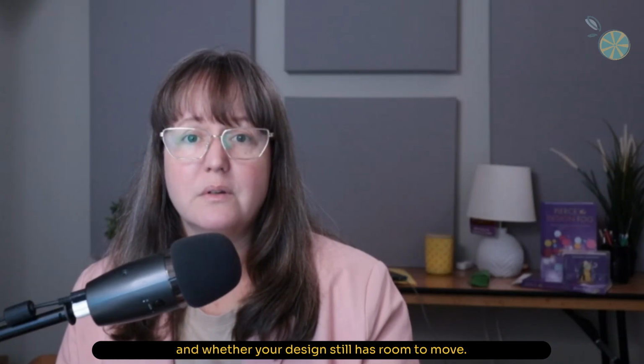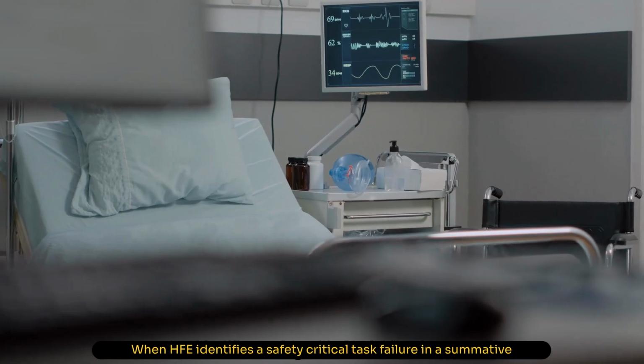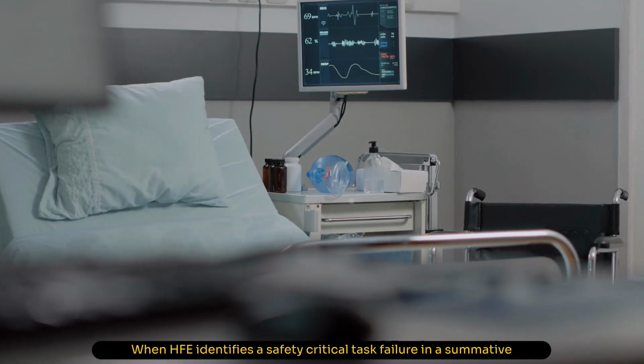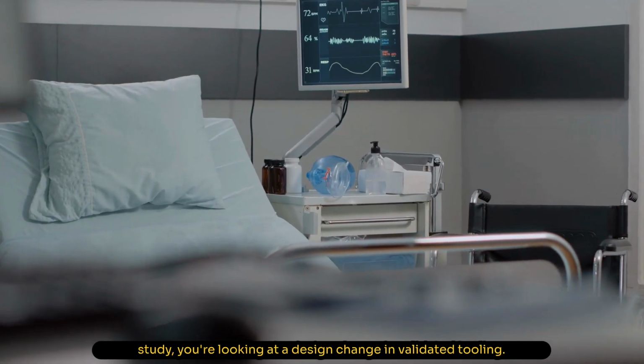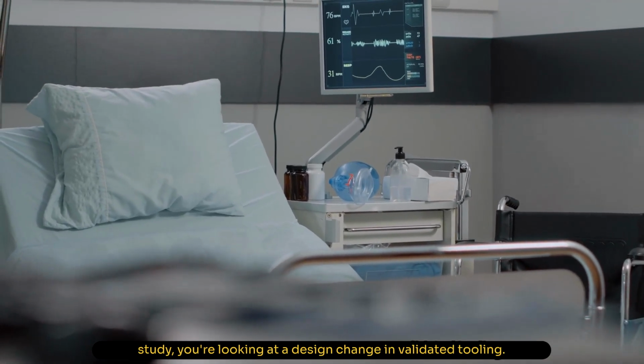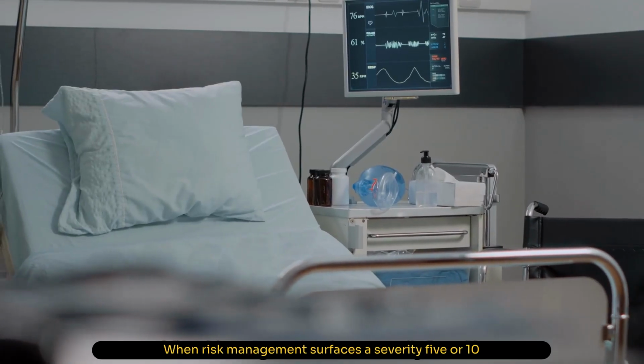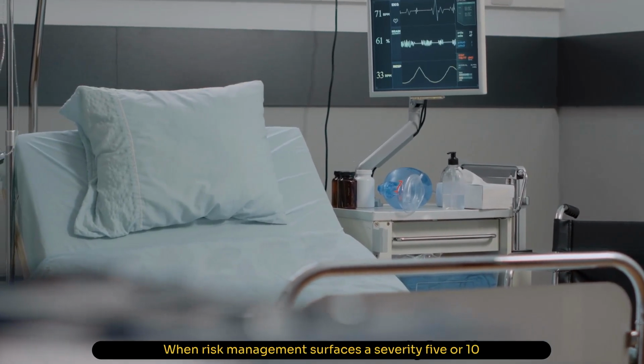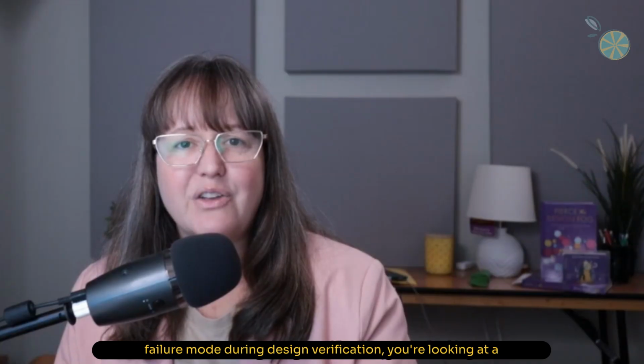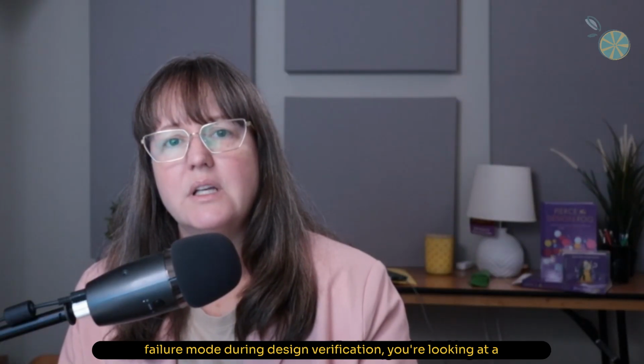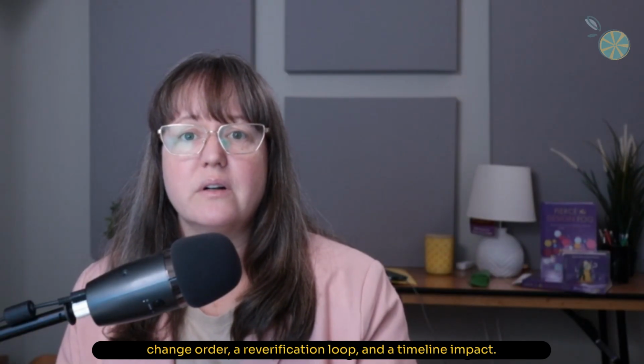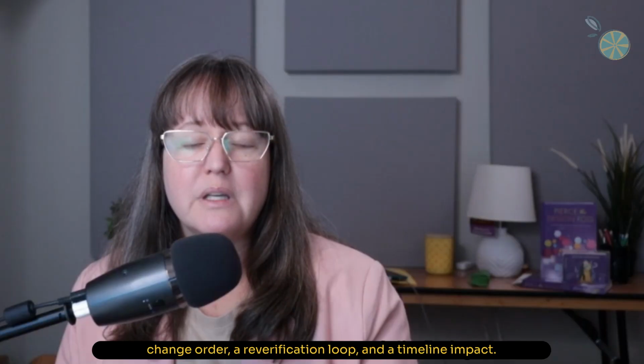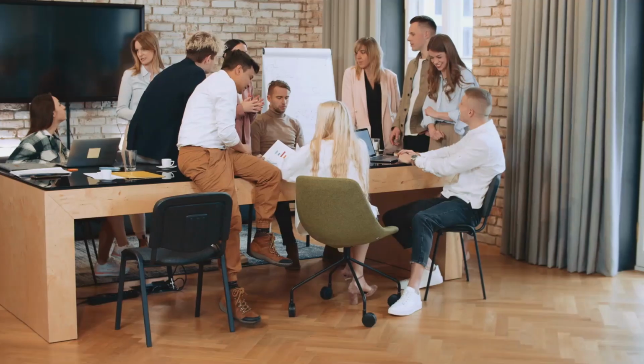to move. When HFE identifies a safety-critical task failure in a summative study, you're looking at a design change in validated tooling. When risk management surfaces a severity 5 or 10 failure mode during design verification, you're looking at a change order, a re-verification loop, and a timeline impact.